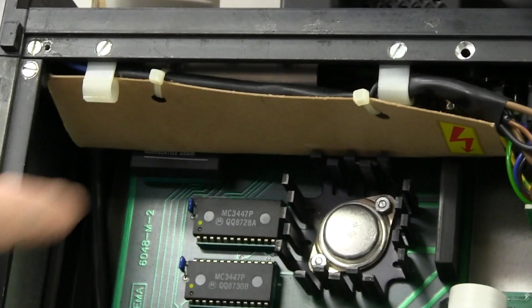Now, whether or not it's still within spec, I don't know, because as I said, there is a non-volatile RAM up here, and that could be keeping the calibration constants in it. I would have to read the manual and see how this works, but presumably it holds the calibration constants in software in there, and during factory calibration or calibration adjustment of this thing, not just calibration check, but calibration adjustment, they would program in those calibration factors into there, so they could be lost.